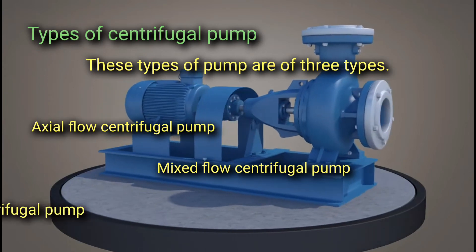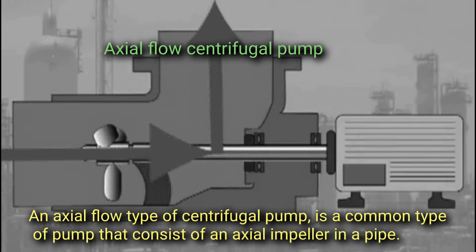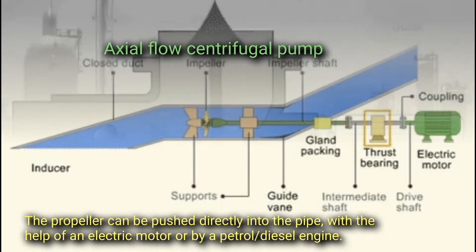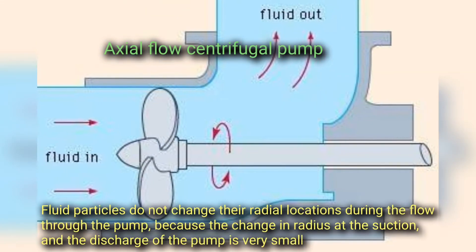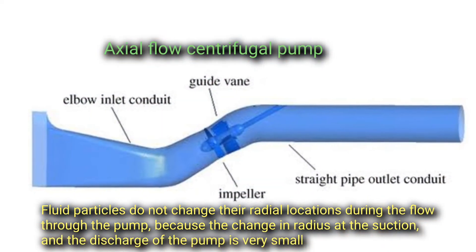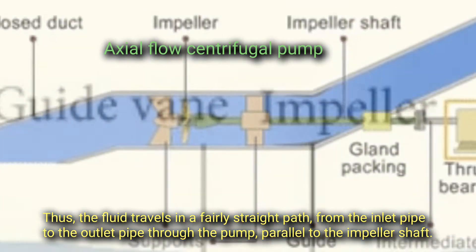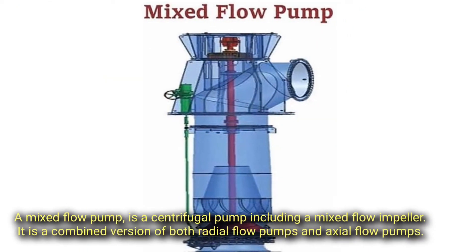Centrifugal pumps are of three types: axial flow, mixed flow, and peripheral centrifugal pump. An axial flow centrifugal pump consists of an axial impeller in a pipe. The propeller can be driven directly by an electric motor or a petrol/diesel engine. Fluid particles do not change their radial locations during flow through the pump because the change in radius between suction and discharge is very small. Thus, the fluid travels in a fairly straight path from the inlet to the outlet, parallel to the impeller shaft.